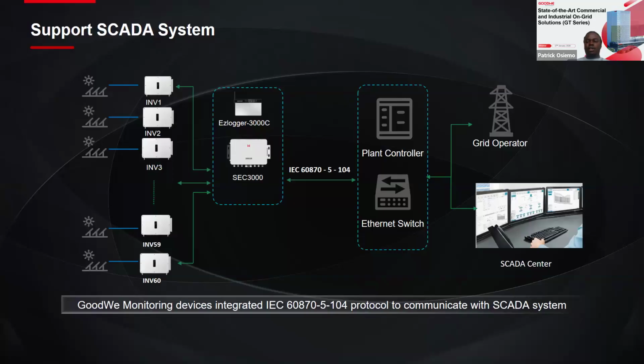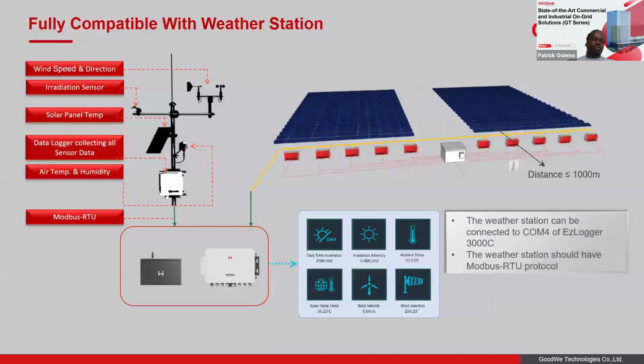For any localized monitoring, we have solutions that can use SCADA and other monitoring protocols like IEC 104 and Modbus TCP, to keep you in touch with localized solutions for your PV installations. For those monitoring the performance ratio of your plants, the SEC3000C allows you to connect weather monitoring stations to track wind speed, direction, irradiance, temperature, humidity, and the like, as long as you're communicating through the Modbus RTU cable to your SEC3000C communication cable. This performance ratio can be monitored through the SEMS Plus monitoring portal.